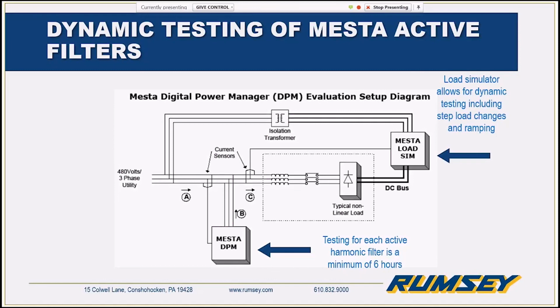Older active filters and some other active filters that are still out there now, they'll have device failures because they'll be trying to output as much power as they think the system needs, which ultimately causes their IGBTs or whatever other devices they're using to fail.